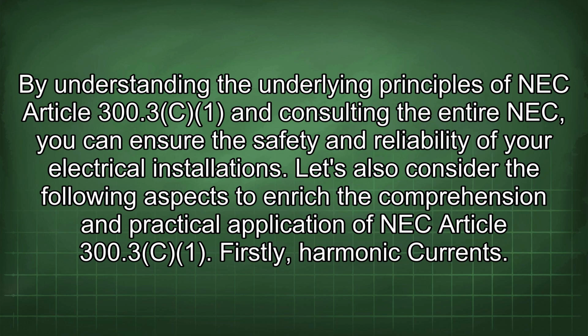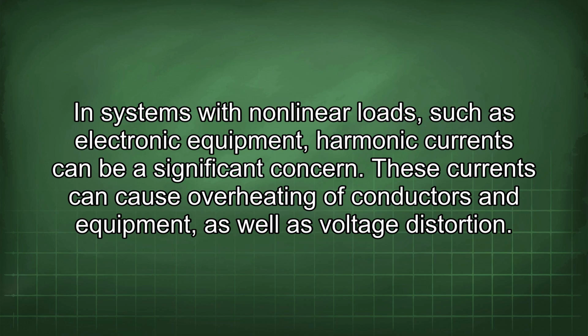Let's also consider the following aspects to enrich the comprehension and practical application of NEC Article 300.3. Firstly, harmonic currents. In systems with nonlinear loads, such as electronic equipment, harmonic currents can be a significant concern. These currents can cause overheating of conductors and equipment, as well as voltage distortion.